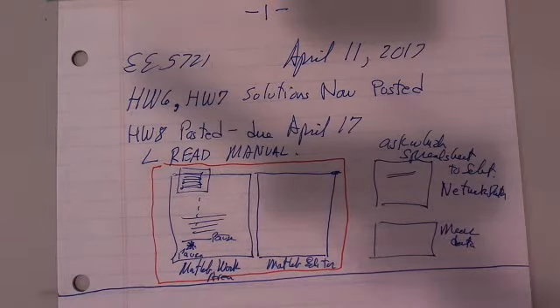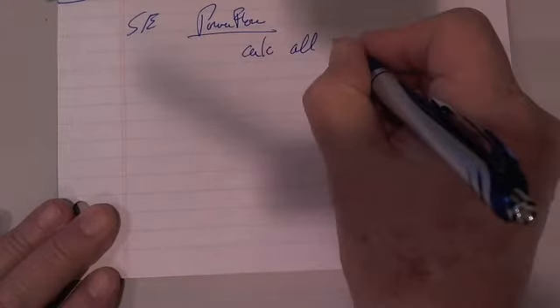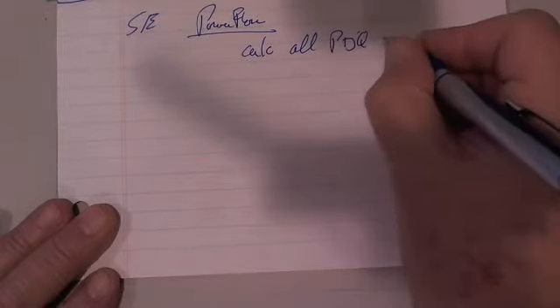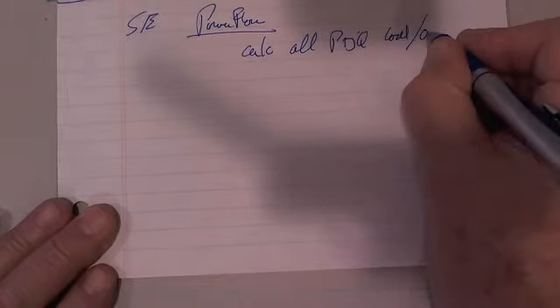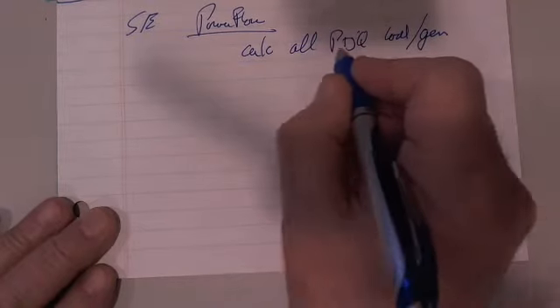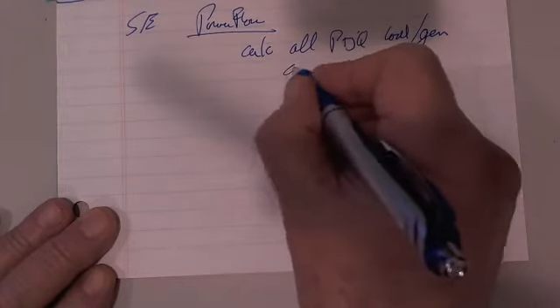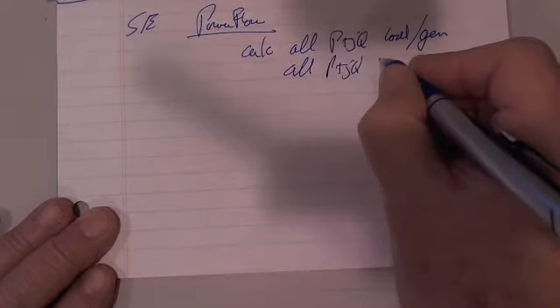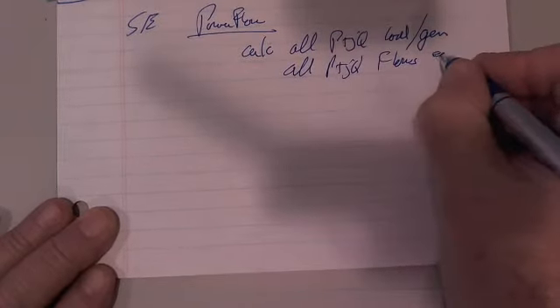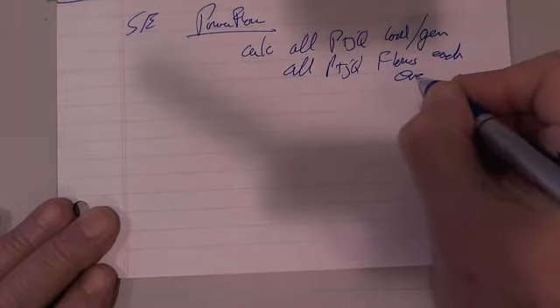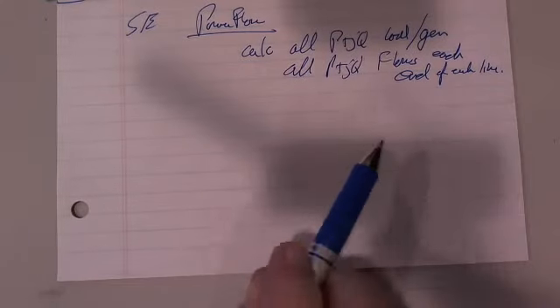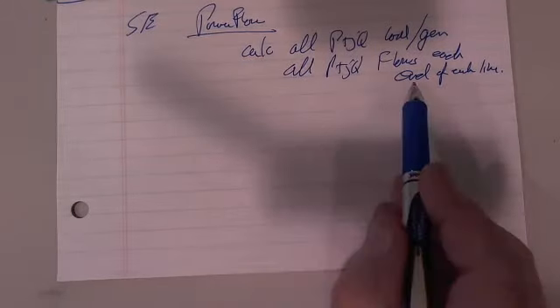There's a program, let me explain this. The state estimator has a power flow, which calculates all of the P plus JQ load, generation, injections, and all P plus JQ flows at each end of each line. So that sort of says that's what the power system's doing.